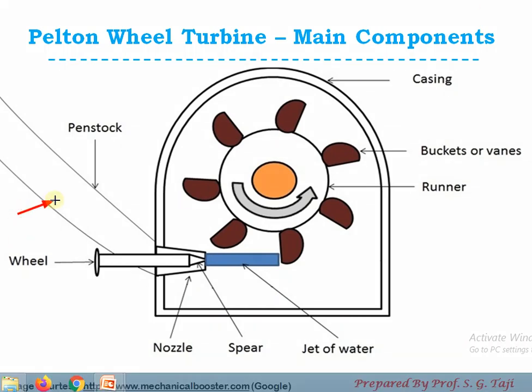The first component is the penstock. Penstock is used to take the water from the reservoir to the inlet of the turbine. At the end of the penstock there would be a nozzle provided — a tapered pipe section where the area of pipe section would get reduced. The function of this nozzle is to convert the pressure energy available in the penstock into useful kinetic energy, so water flowing through this nozzle gets accelerated and strikes on the bucket in the form of a jet with high kinetic energy.